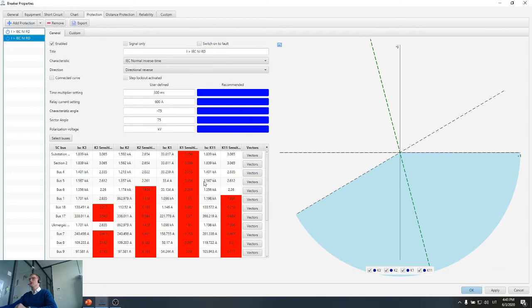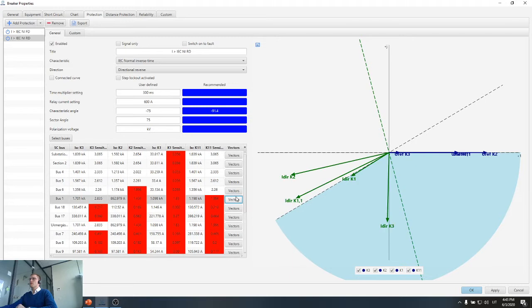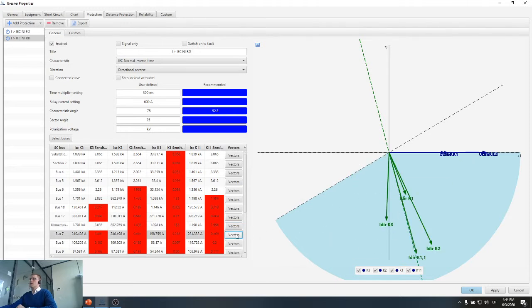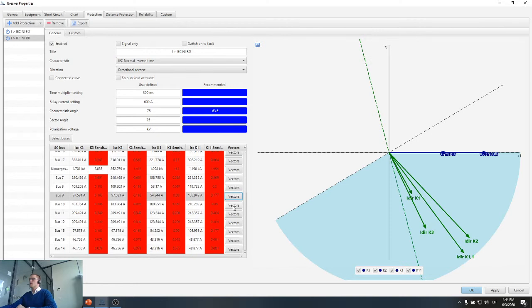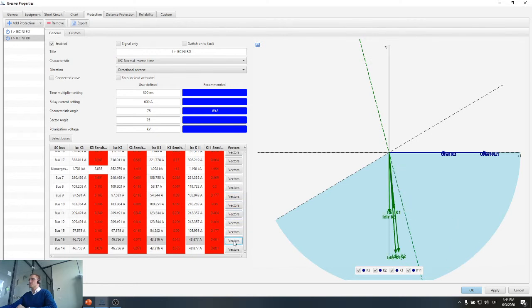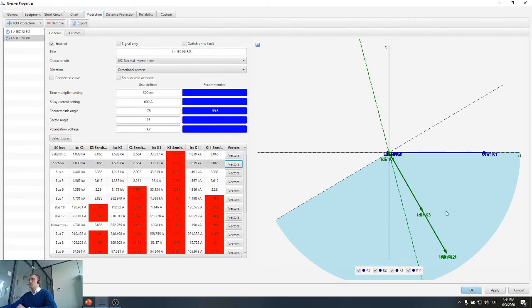In case of reverse directional protection device, I have many more vectors, of all the short circuits that are happening in the network. So I have selected my operation zone so that the directional protection device will sense most of the short circuits in there. So we can see that all those vectors are mostly in the blue zone, which says that with these settings, my directional protection device will correctly measure the direction of the current, and it will trip with different times.